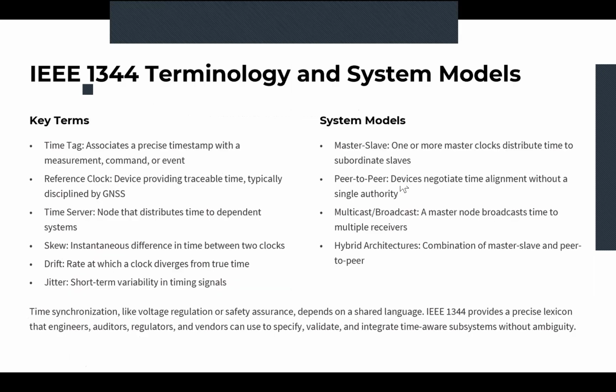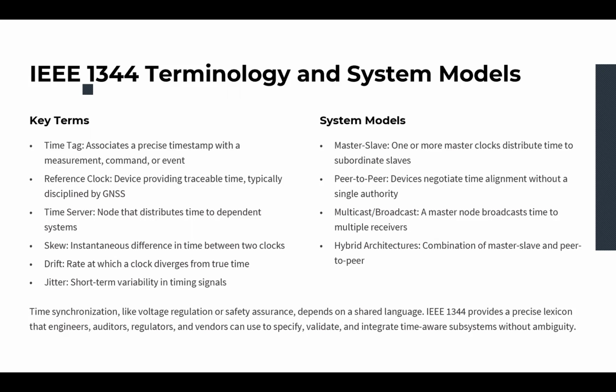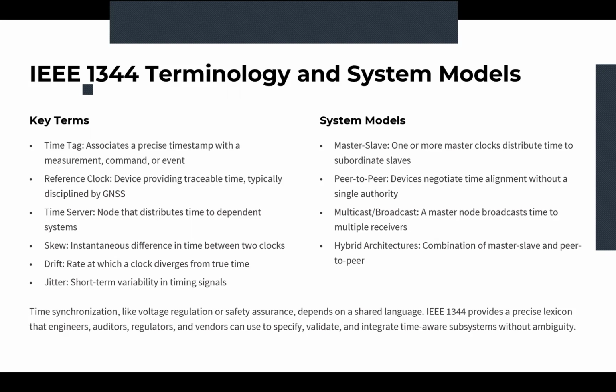Now, there are several important terminologies that we have to pay attention to when we talk about this standard and time synchronization. We are going to go over some of the important terminology because we want to have common ground. When we talk about a time tag, we want a common definition so it's specific and there is no ambiguity. Let's start with the key terms that we are going to use in IEEE 1344. The first one is time tag.